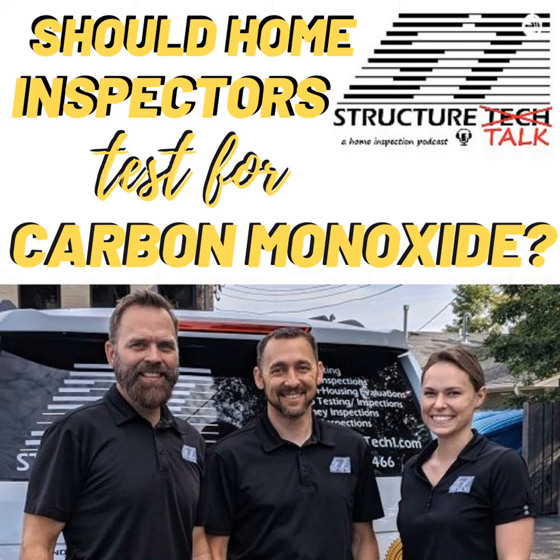Now, we don't calibrate our stuff religiously once a year. We cross-check our equipment against equipment that has been calibrated at least monthly. We are always cross-checking our equipment with other known good equipment, and we send them in for calibration probably about once every 2 years. But we're always double checking it to make sure they're accurate.